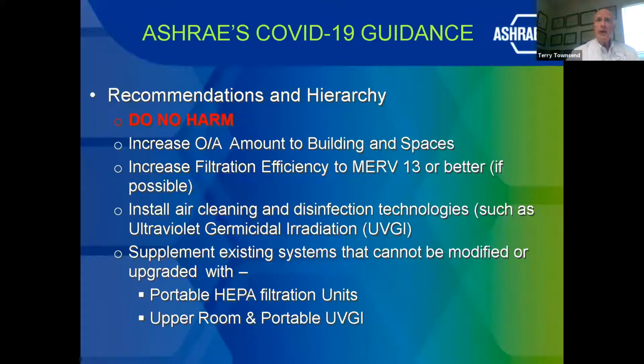So now ASHRAE's guidance is, first of all, to do no harm, but we want to increase the outside air amount to the buildings and spaces, as well as increase the filtration efficiency, and install air cleaning and disinfection technologies, especially UV germicidal irradiation. And if you can't do this with existing HVAC systems, then upgrade with portable HEPA units or upper room and portable UVGI units.